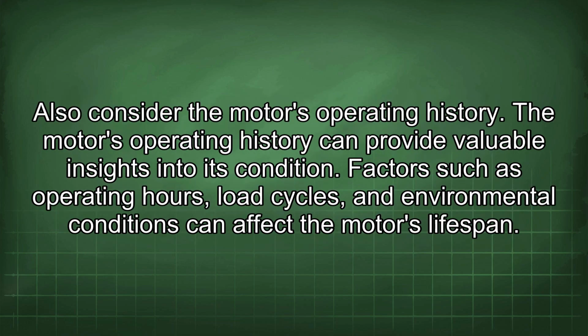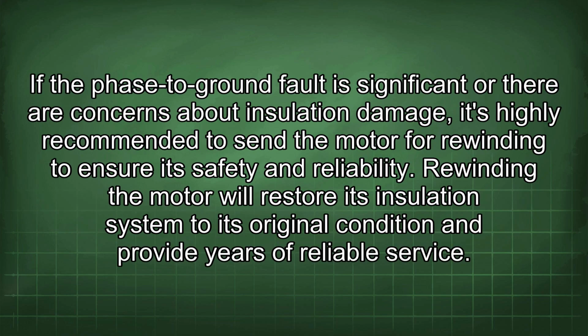Also consider the motor's operating history. The motor's operating history can provide valuable insights into its condition. Factors such as operating hours, load cycles, and environmental conditions can affect the motor's lifespan. If the phase to ground fault is significant or there are concerns about insulation damage, it's highly recommended to send the motor for rewinding to ensure its safety and reliability. Rewinding the motor will restore its insulation system to its original condition and provide years of reliable service.